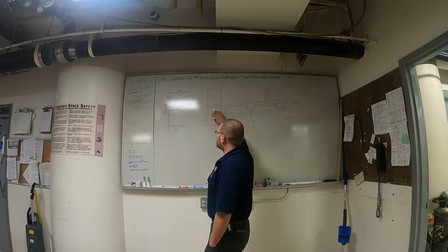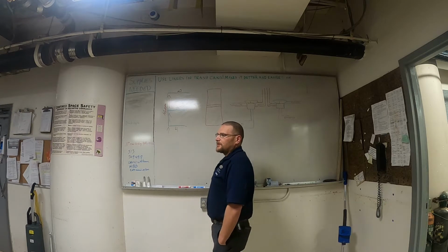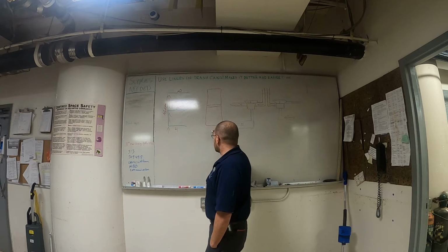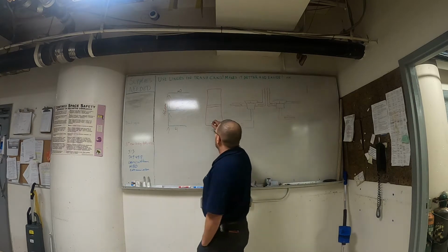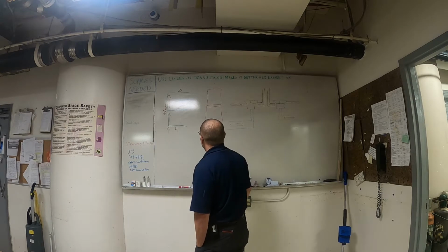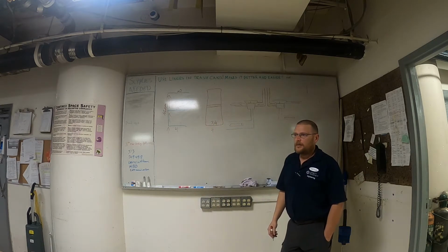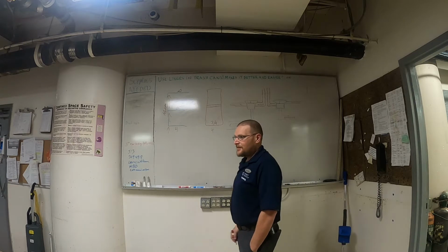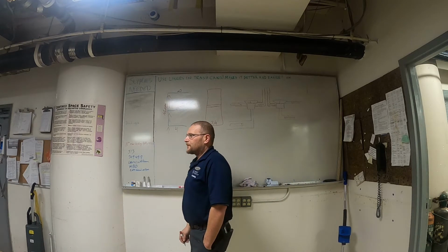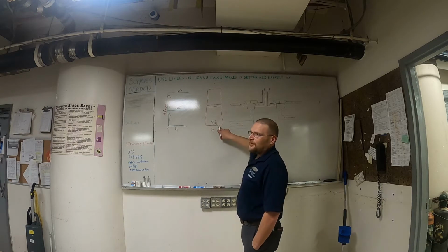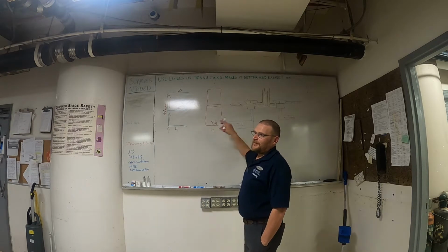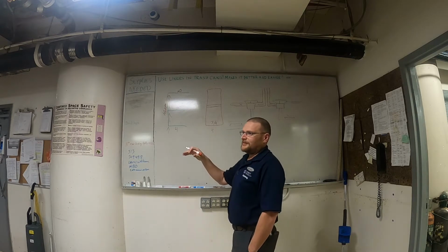Now, the red, the 8, what is this? Hot water. Okay. Now on the 4th floor, what size line do you have? 3/4. Why is it only 3/4 on the 4th floor? Recirc. 4th floor only has recirc.